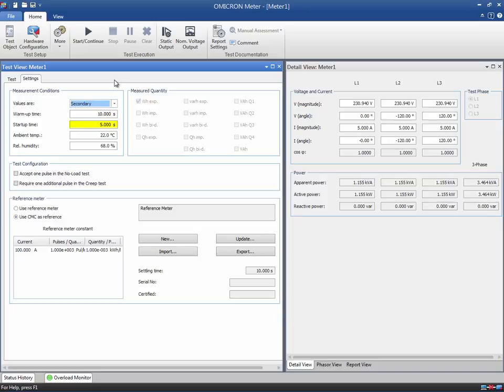During this period, all the test parameters are output without starting the meter pulse recording. Keep in mind that this time cannot be lower than the settling time defined in the test object. This way, we can ensure that the meter stabilizes before starting any measurements.